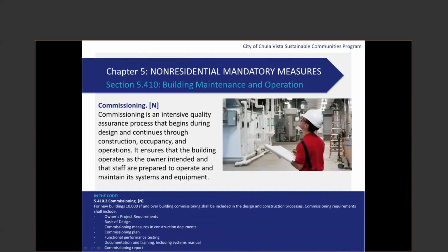As California's building code gets more advanced, especially as the energy code requires our buildings to be higher performing, we end up relying on the proper functioning of our building systems, such as HVAC, irrigation, appliances, and utilities. So for buildings over 10,000 square feet, CalGreen requires commissioning. This process is shown to result in a 5 to 10% energy savings in your building.